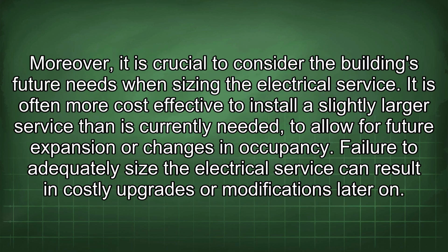Moreover, it is crucial to consider the building's future needs when sizing the electrical service. It is often more cost-effective to install a slightly larger service than is currently needed to allow for future expansion or changes in occupancy. Failure to adequately size the electrical service can result in costly upgrades or modifications later on.